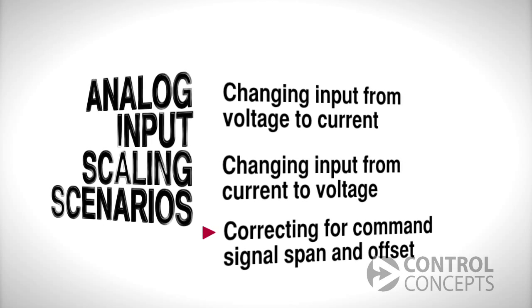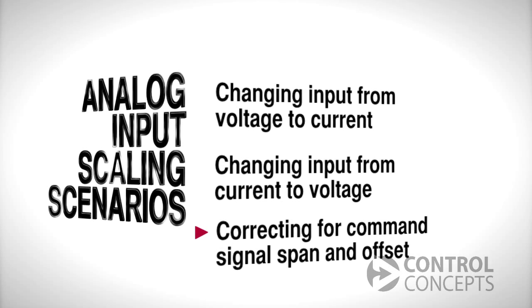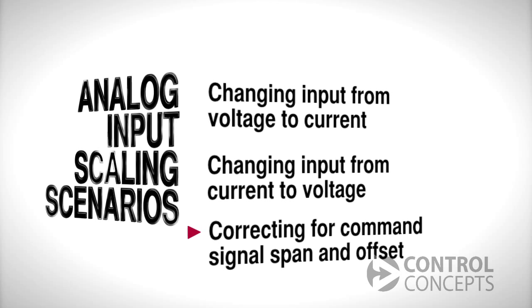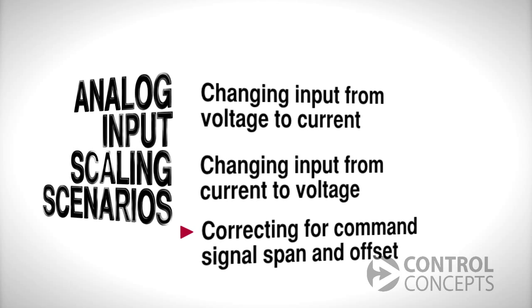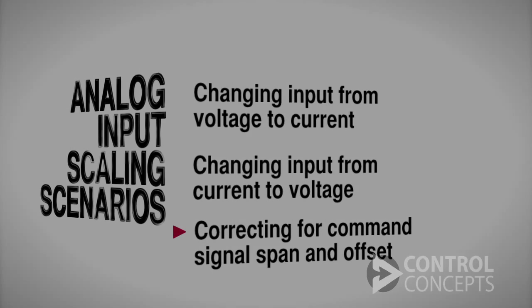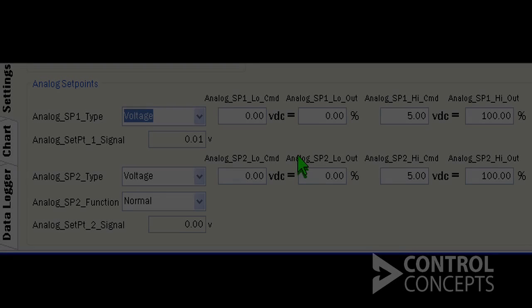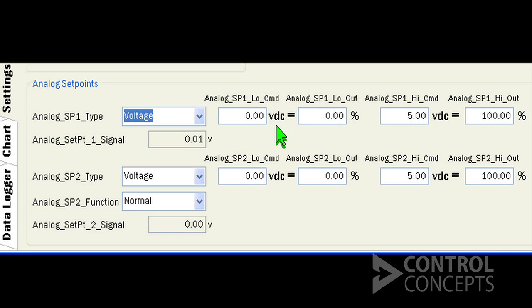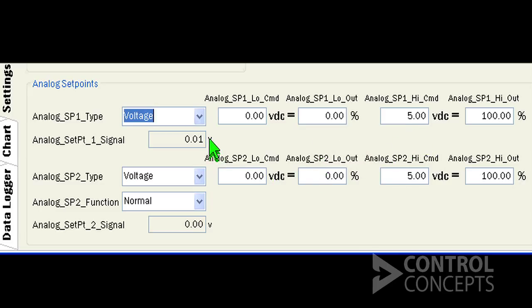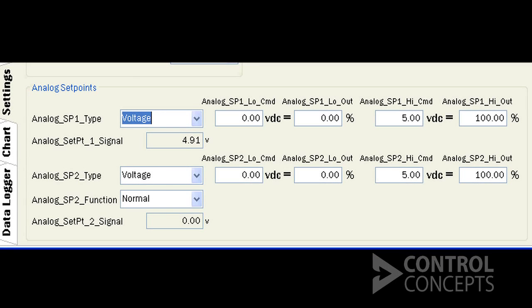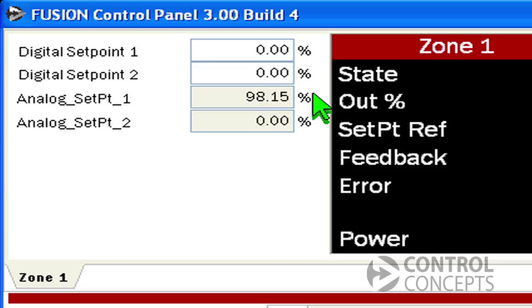Finally we will correct for span and offset on analog command signals. Nominally our PLC should output 0 to 5 volts per command signal, but in reality it's only running at 0.01 in off state and 4.91 in full on state. We can see the effect in the upper left corner.